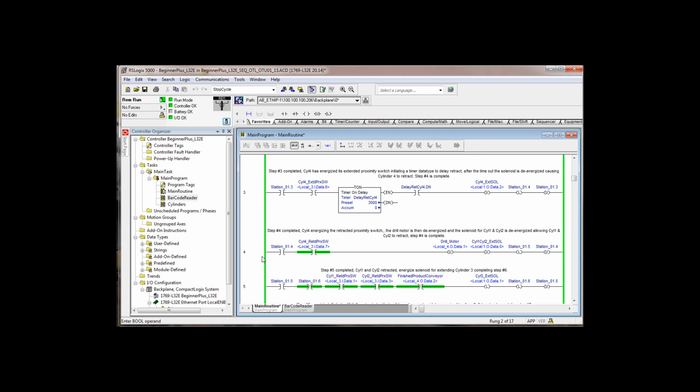At this instant in time, and remember, this all doesn't happen in one program scan. Here we unlatch that output bit that caused cylinder 4 to extend. Whether in the real world with a real cylinder, 1 or 2 seconds that it takes to retract to make this prox here in rung 4, or the timers that we're using in our cylinders program, it's the same thing.